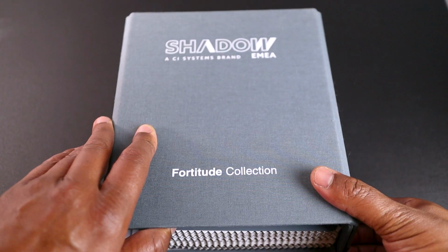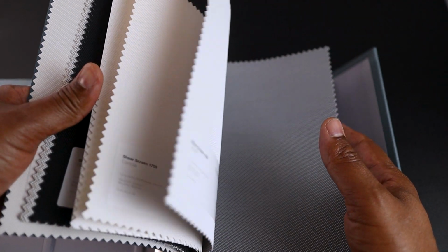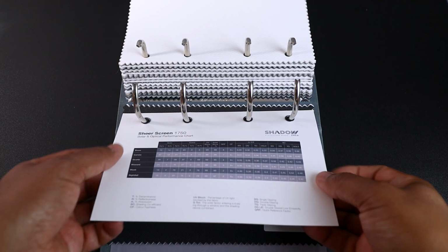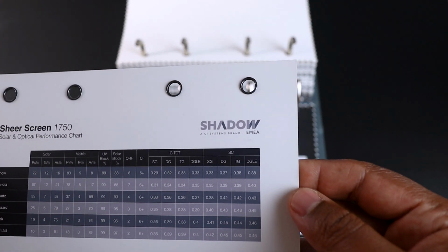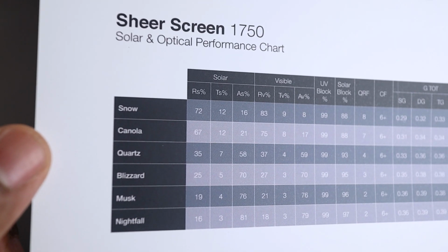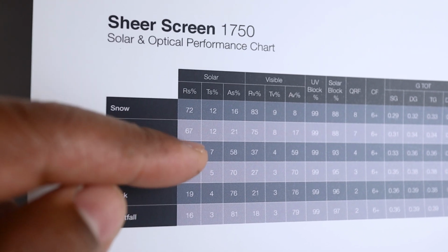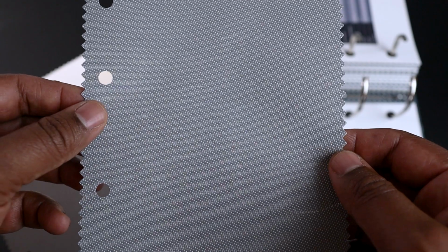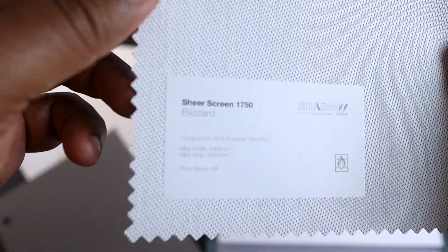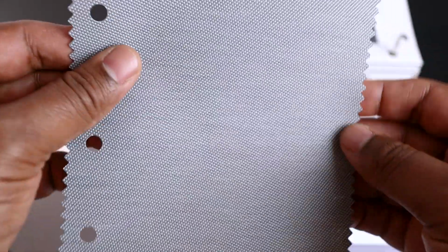So, for example, if I need to specify roller blinds sheer fabric in a meeting room or a workspace where the windows are south-facing, meaning that they receive direct sunlight most of the day and therefore increases glare and heat gain, leading to high cooling cost, I would choose a fabric with a low TS, like between 5 to 10%. It will help reducing the HVAC cooling load and will minimize glare on screens, making the space more comfortable for the occupant, saving energy with better visual comfort during video calls or presentation.